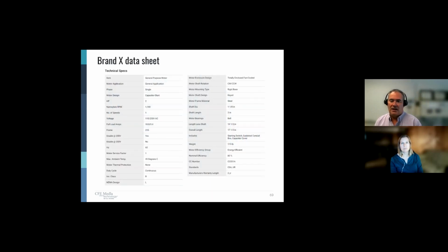This is a data sheet that I pulled off of a manufacturer's site. And this is the technical specs for their motor. And in this case, this is a simple single phase 2 horsepower capacitor start motor. And look at all of the things we have to choose, okay, or ignore. And you ignore them at your own risk. You know, what's the RPM? How many speeds does it have? What voltage does it operate? We talked about. There's our full load amps.